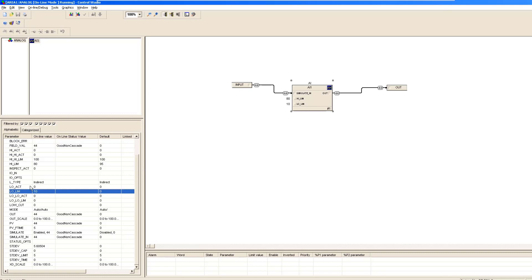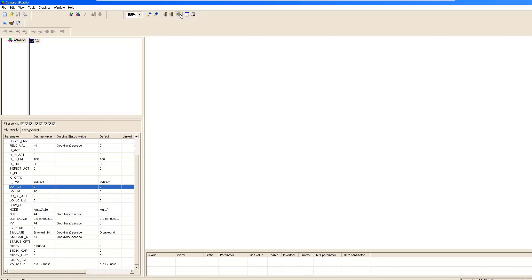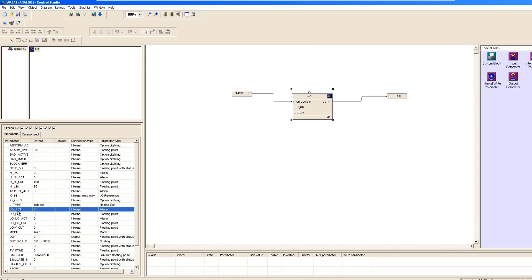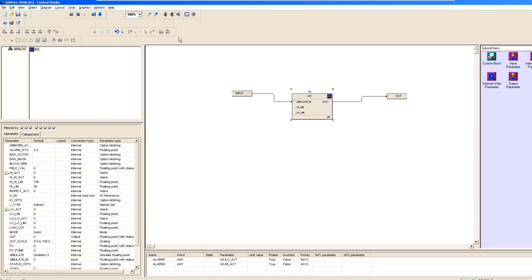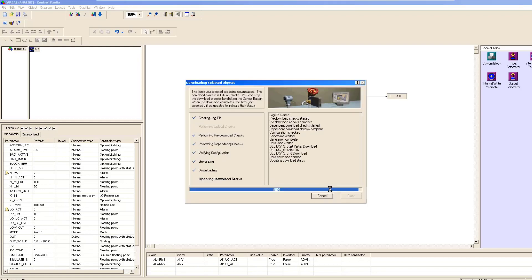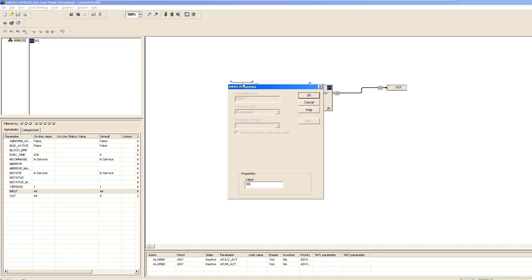To do that, you have to make it offline first. Then right-click and assign alarm for the Low Activation Alarm — you can see it's already activated. Then right-click and assign the High Activation Alarm. After that, download — select all, click OK, click OK — then click OK, select Yes. Now make it online.